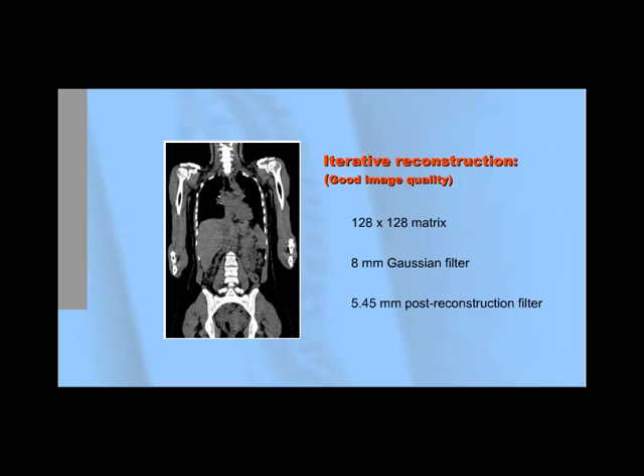iterative image reconstruction ensures good image quality. The study is reconstructed iteratively, utilizing the entire 128x128 matrix, an 8mm Gaussian filter, and a post reconstruction filter of 5.45mm.